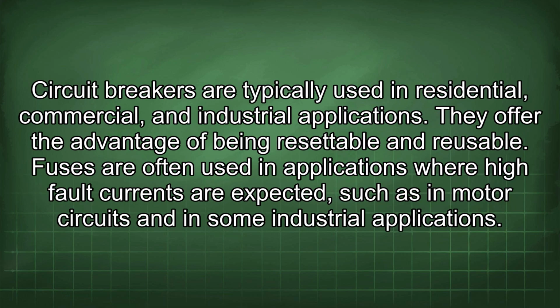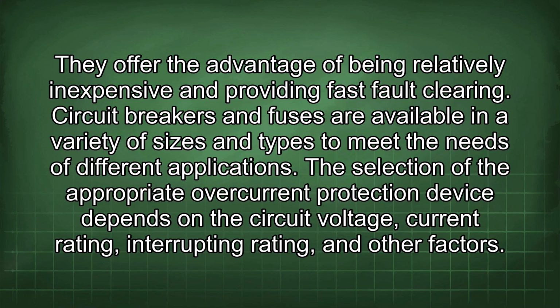Circuit breakers are typically used in residential, commercial, and industrial applications. They offer the advantage of being resettable and reusable. Fuses are often used in applications where high fault currents are expected, such as in motor circuits and in some industrial applications. They offer the advantage of being relatively inexpensive and providing fast fault clearing.